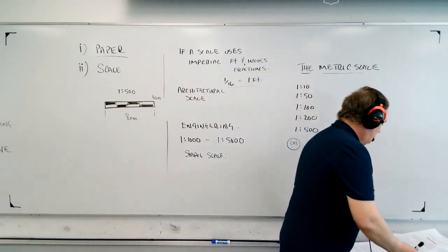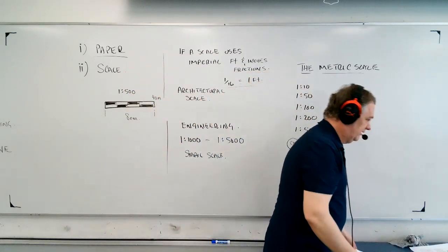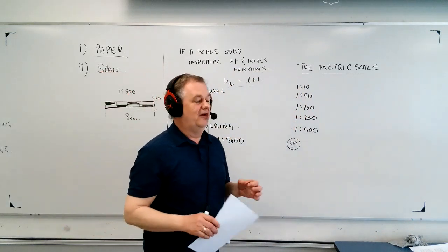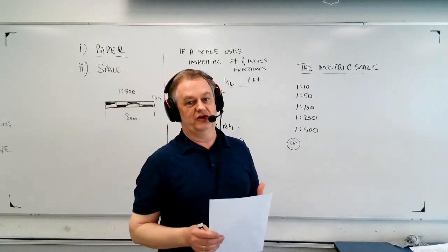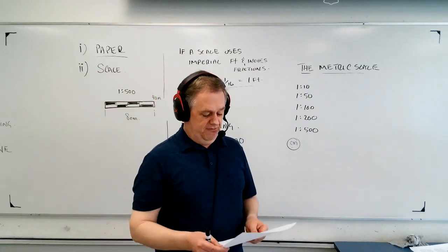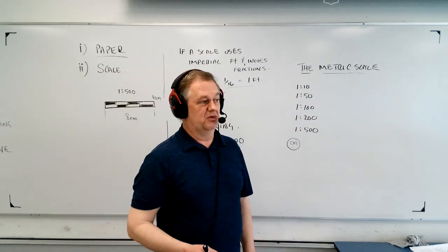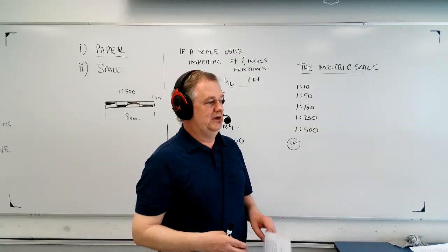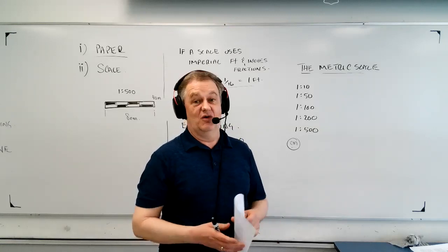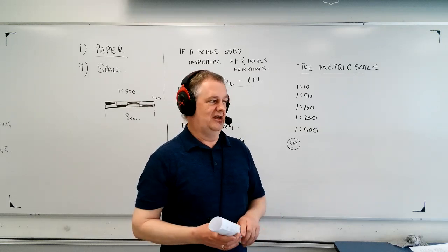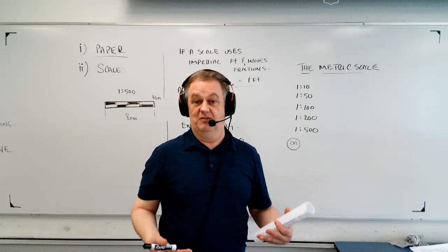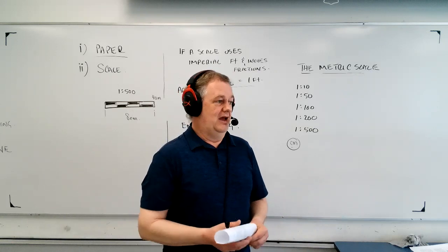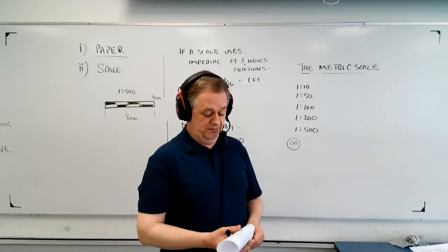So copying of prints is normally something that you try and avoid for a couple of reasons. The quality tends to deteriorate, the resolution goes down, and it doesn't take very long before you can have some real problems with it. And secondly is the scale. If the scale changes, not everybody's aware of that. Somebody could easily do some type of takeoff where you measure how much TECK cable or how much wire you need, and you can come up with wrong numbers, and it's going to cost money for sure.